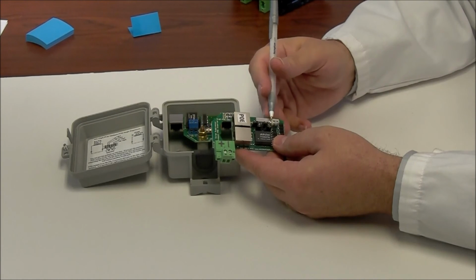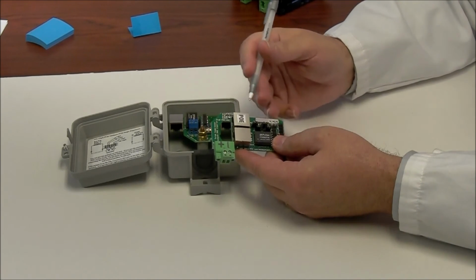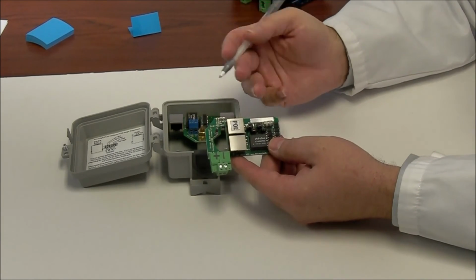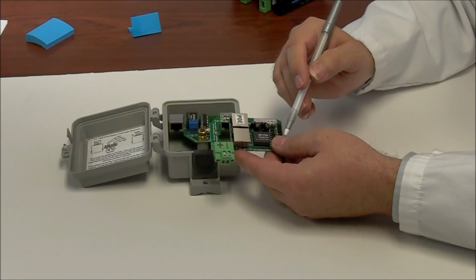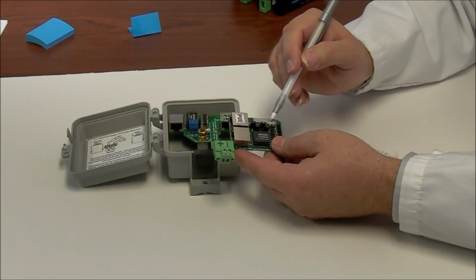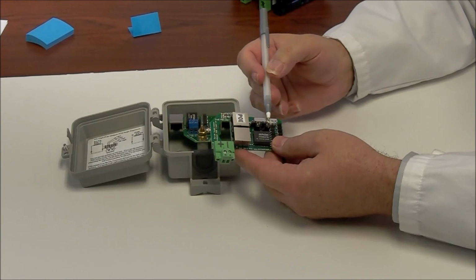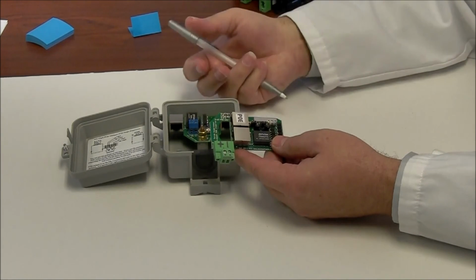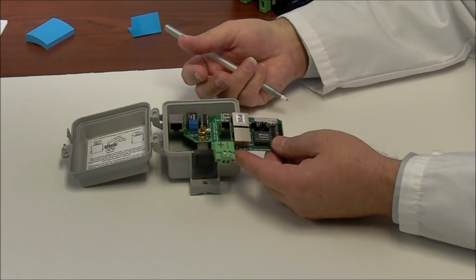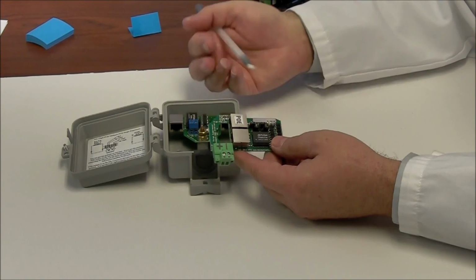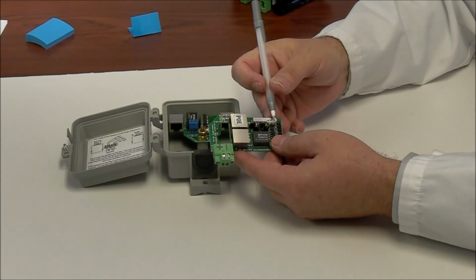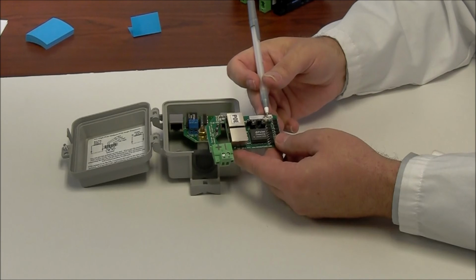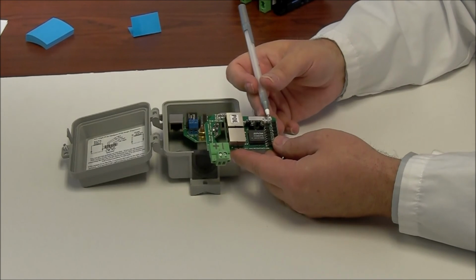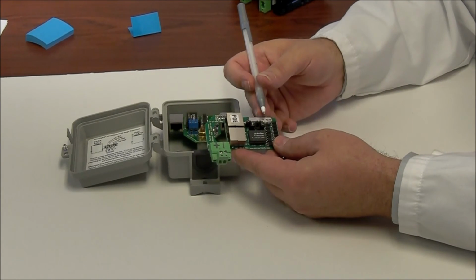And once you have a lot of free electrons in there, this thing basically just becomes a dead short circuit to ground. So all of these surges that we funneled through all of these steering devices to these ends, once these gas tubes fire, you're just shorting it to ground, and that's where you want your impulse to go. These things will take multiple hits. Nobody will say how many, because every hit's different - different current, different voltage - but they do survive.